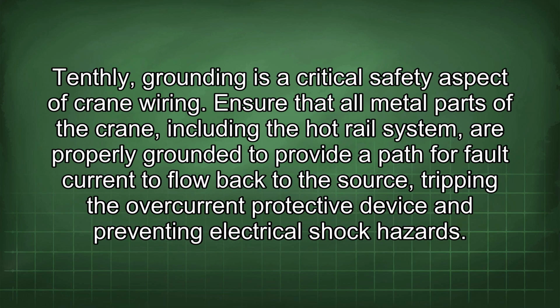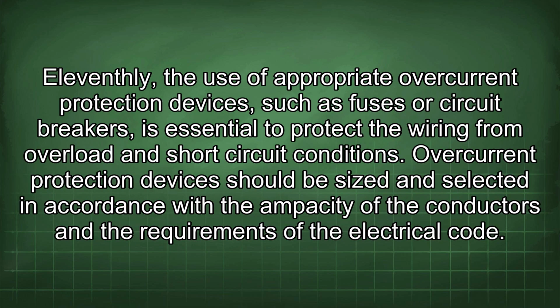Tenthly, grounding is a critical safety aspect of crane wiring. Ensure that all metal parts of the crane, including the hot rail system, are properly grounded to provide a path for fault current to flow back to the source, tripping the overcurrent protective device and preventing electrical shock hazards. Eleventhly, the use of appropriate overcurrent protection devices, such as fuses or circuit breakers, is essential to protect the wiring from overload and short-circuit conditions.